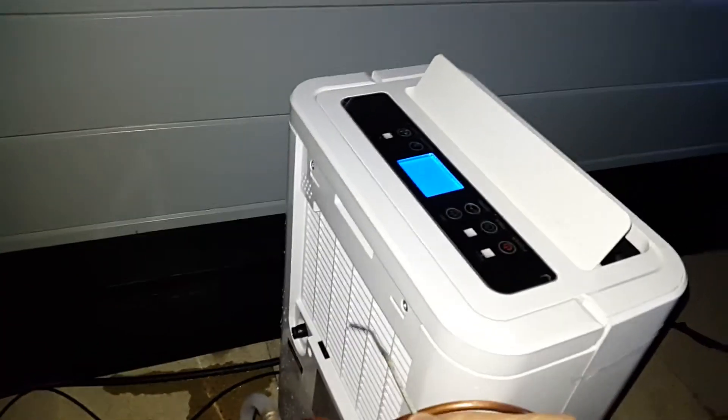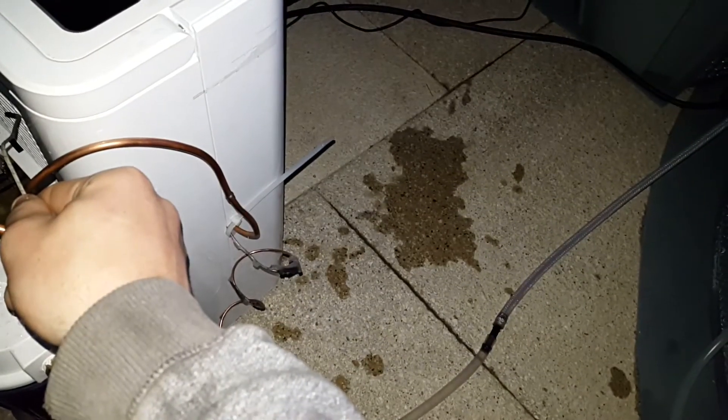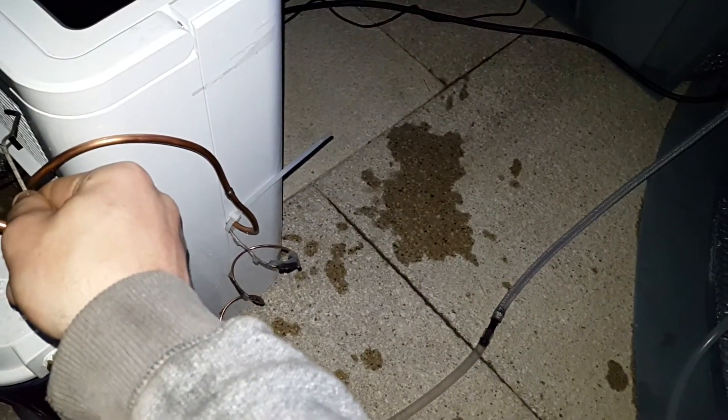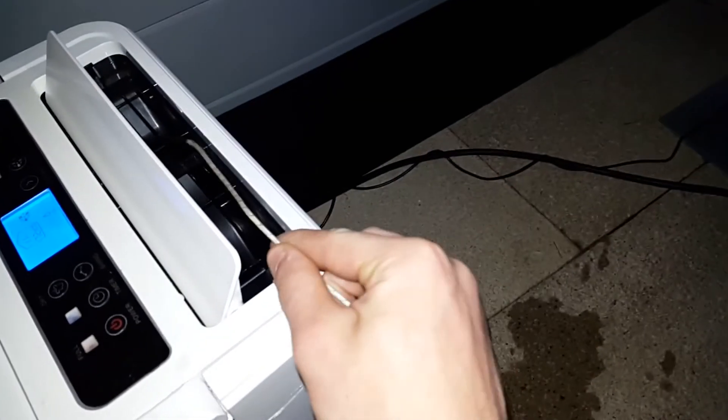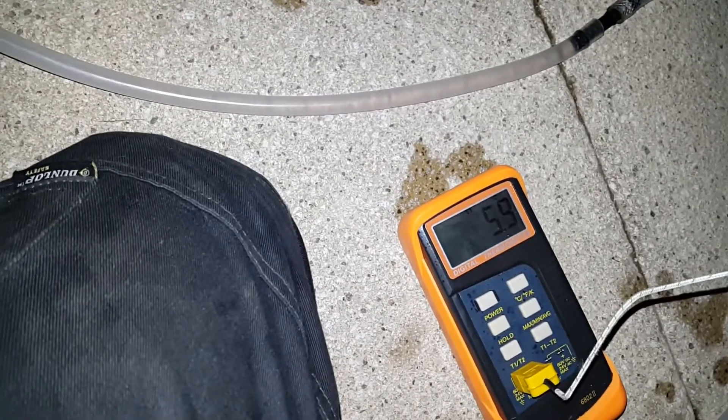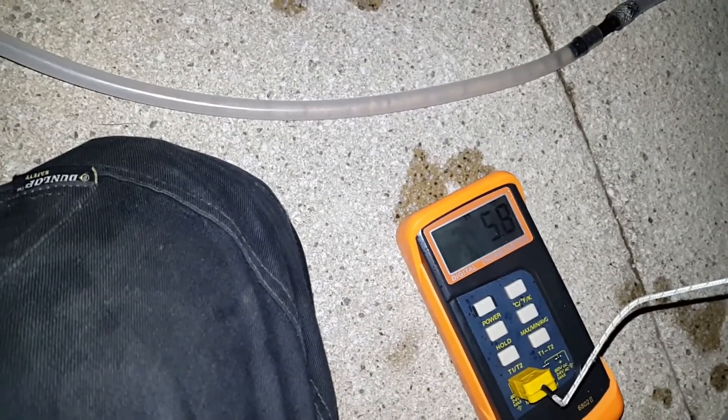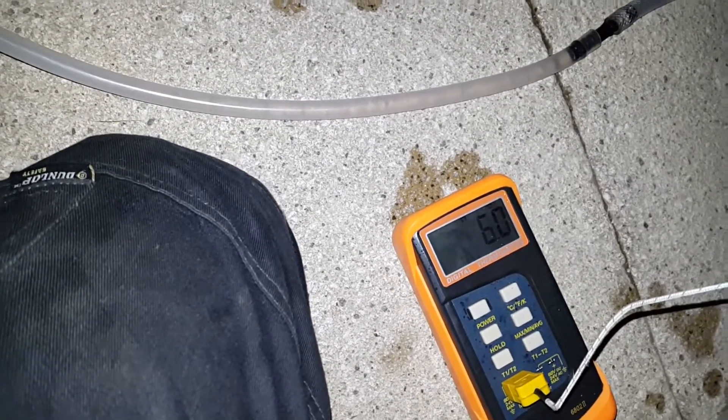OK, so let's measure the temperature of the air going in to the heat pump. It seems to be about 12.6 in the air coming out. Let's see what that drops to. 5.96 degrees celsius, the air going in. Yeah, it's taking quite a lot of heat out there.